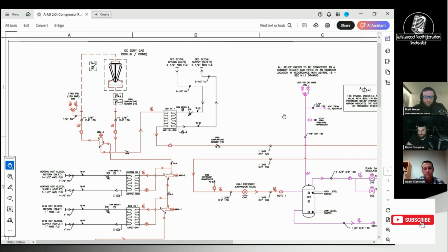So are you guys using CTR valves, or are you guys using automated ball valves to do it? Ball valves. So is it like a float? Would it be better to float the opening, where it's slowly opening, slowly closing, so it's not forcing it? If it was a floating actuator, it wouldn't hit so hard, it wouldn't just be on off? Quite possibly, but I think where the challenges we have is, and I think that goes back to pressure control, which might be very advantageous to get good quality and stable control using temperature.